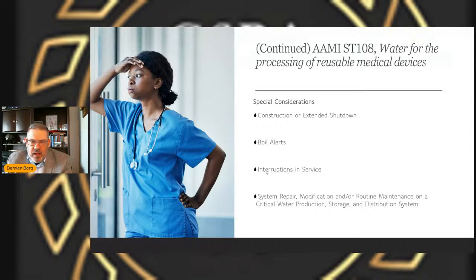What's going on? Because if you start having staining issues, black flakes, pitting, any of those issues we've all heard around in the news, where's it coming from? Is it coming from your sink? Coming from your washers? Coming from your sterilizers? Is it quality? Is it the steam dryness? We don't know until you know a baseline. And what happens is if you don't have a baseline and you start to have problems, where do you start?